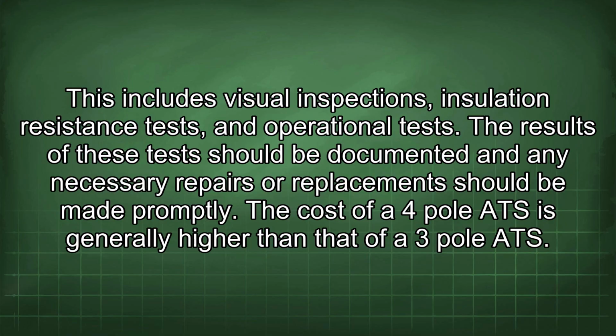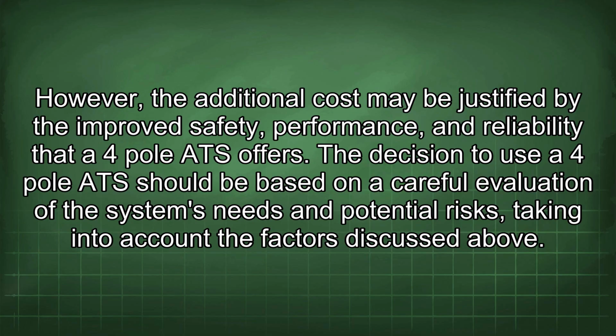The cost of a 4-pole ATS is generally higher than that of a 3-pole ATS. However, the additional cost may be justified by the improved safety, performance, and reliability that a 4-pole ATS offers. The decision to use a 4-pole ATS should be based on a careful evaluation of the system's needs and potential risks, taking into account the factors discussed above.